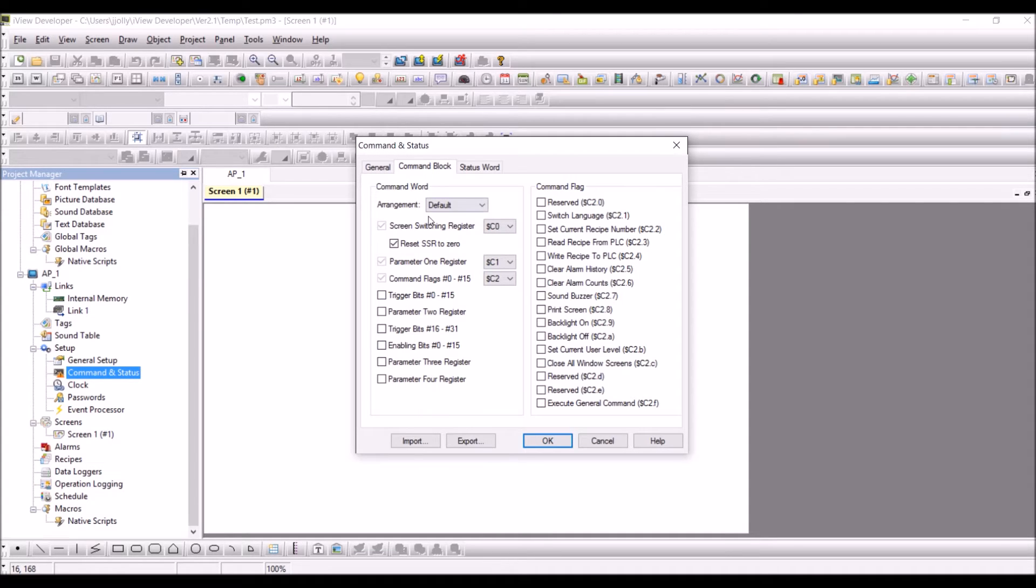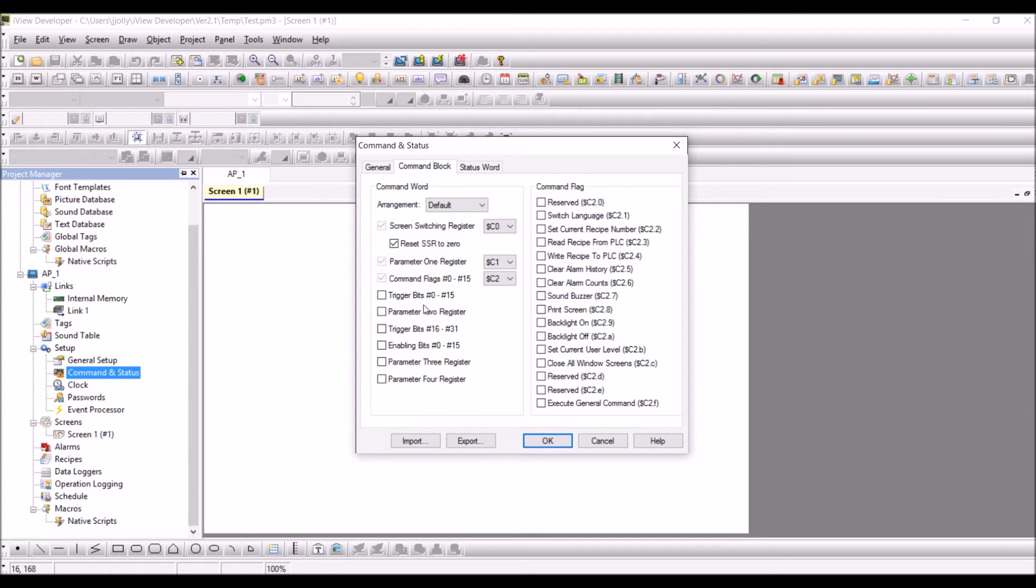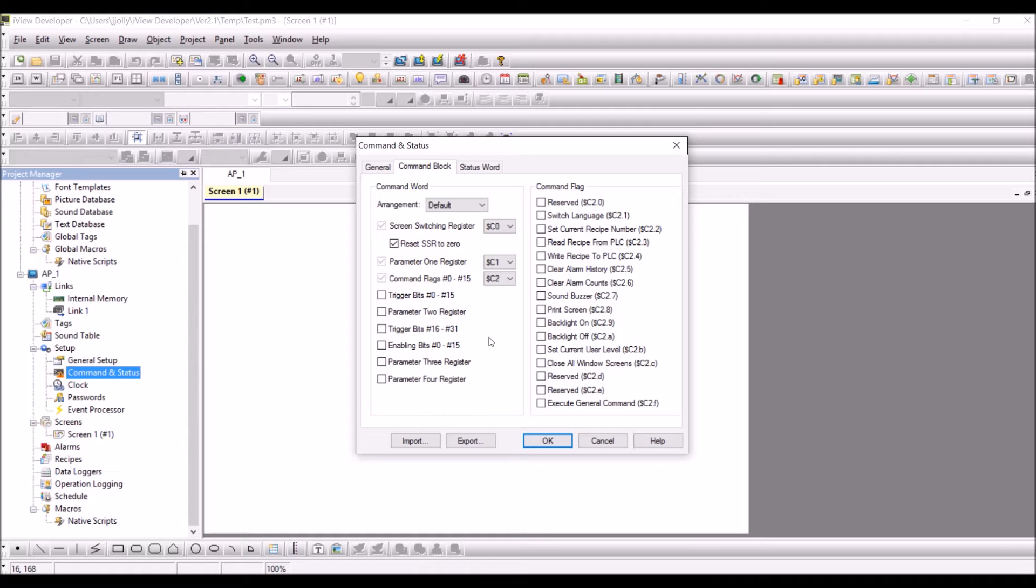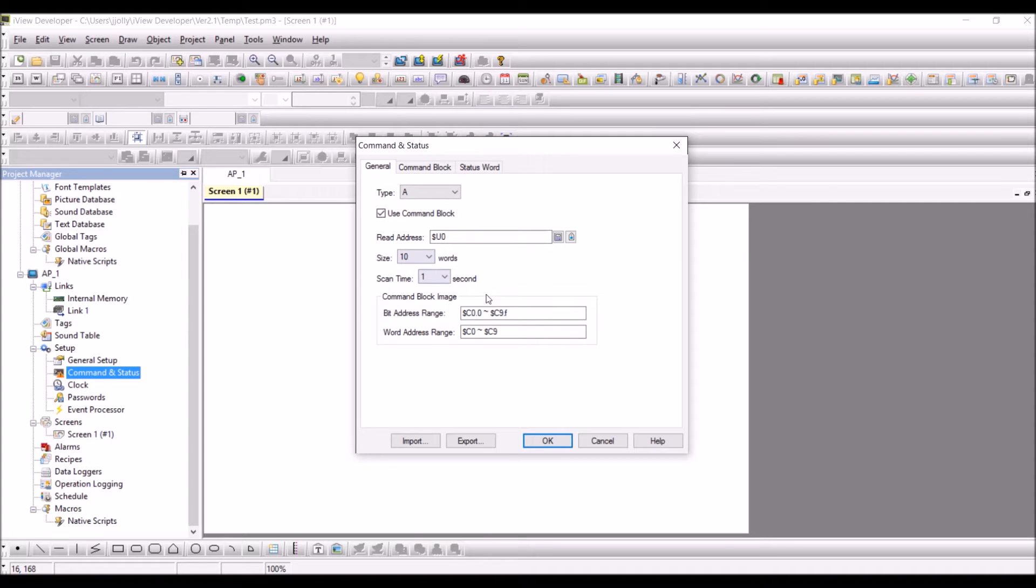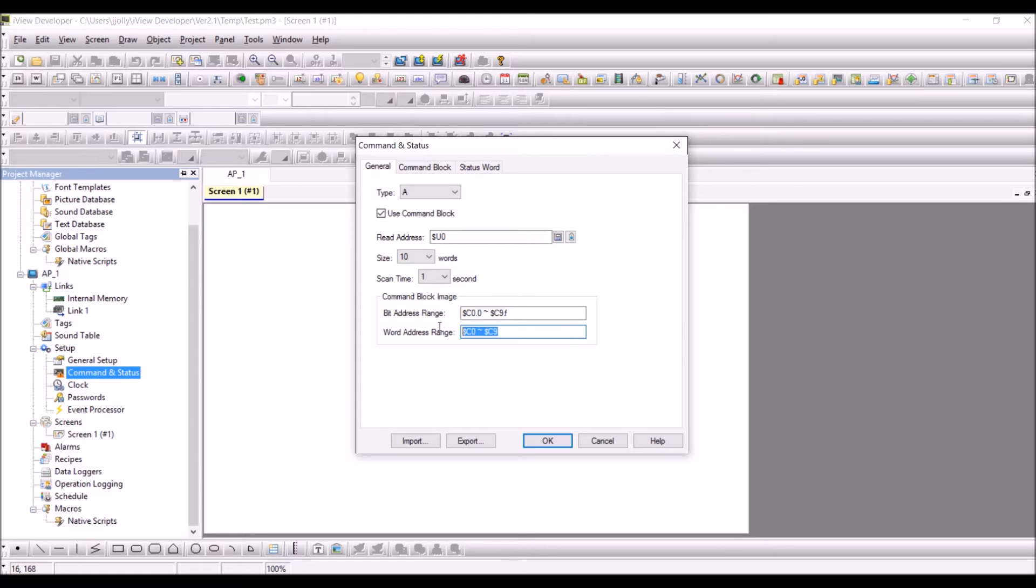So now you do have the command word. If you look at the command word we do have one two three four five six seven eight nine, so we do have nine registers for this one. So it takes the first register from C0. So if you go to the general, C0 is the word address range and it takes C0 to C9. So it will take 10 registers there because we do have 10 registers here configured.